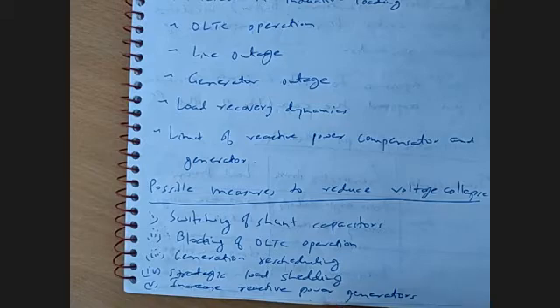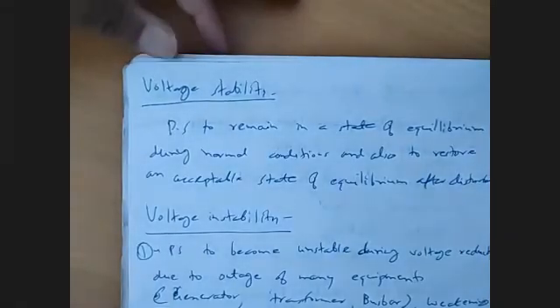That means we will remove load in a strategic manner so that the system reactive power is not affected much. It will be a small disturbance change, and due to that the possibility of voltage collapse can be reduced. Or we can increase the reactive power generation of the generators in the system, so the reactive power requirement of the system can be met and the possibility of voltage collapse will reduce.